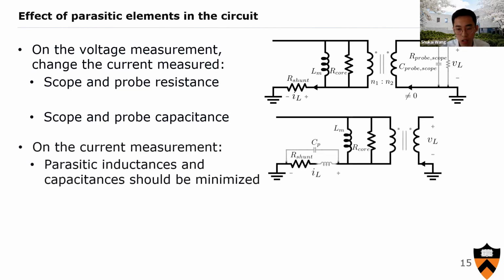Now the second thing is on the current side. We have a current shunt measurement, which guarantees very high accuracy for current measurement. But nonetheless, parasitic capacitance and inductance will be present in this shunt resistor, especially the parasitic inductance in series with it. This inductance may introduce a voltage drop, so what you measure through the current shunt may no longer be the true current exciting the core from the previous stage, introducing error. But the coaxial shunt we selected is rated for 800 megahertz, and our operating frequency only goes up to 500 kilohertz, so it's not so worrisome for our case.